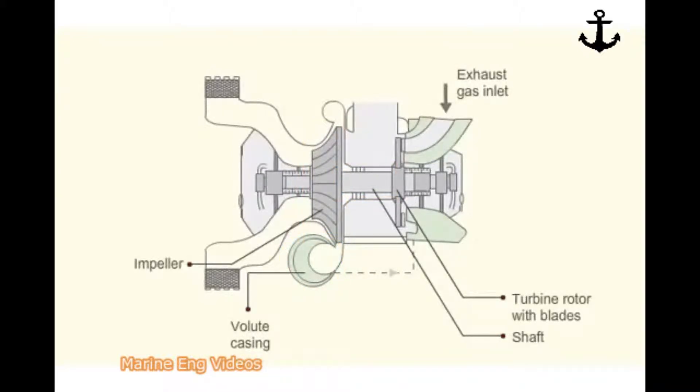The exhaust gas enters the water-cooled turbine casing through a grid which prevents any broken pieces of piston ring from entering the turbine. The exhaust gas passes through nozzles where the pressure energy is converted to kinetic energy. The gas impinges upon the turbine blades, rotates the turbine wheel and comes out of the exhaust gas outlet.